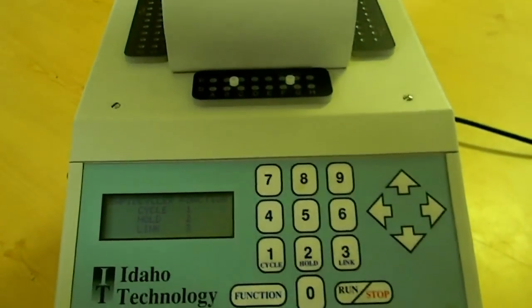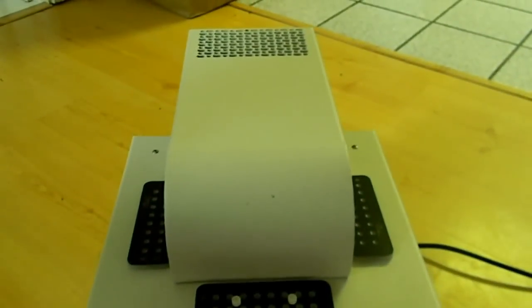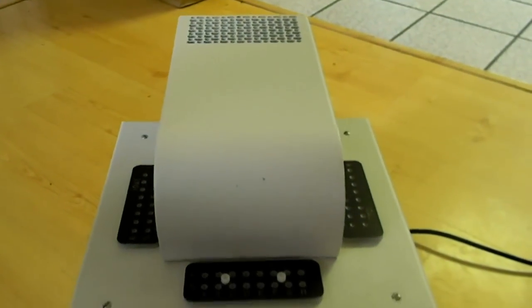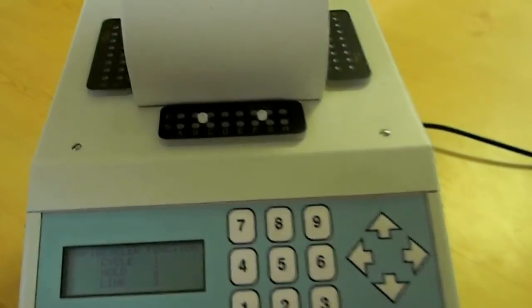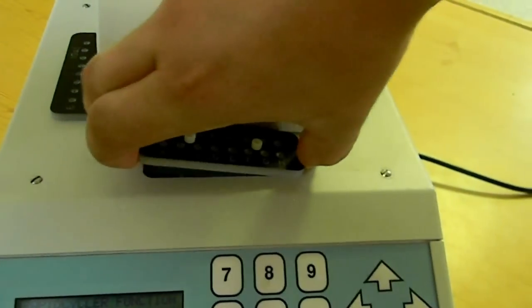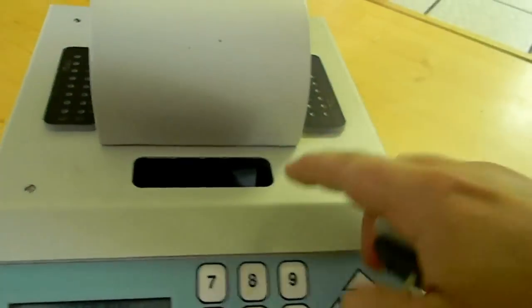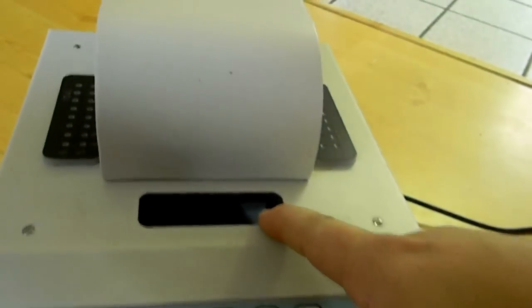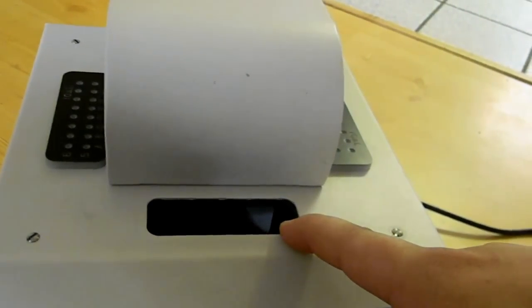Now this machine is a little different than conventional PCR machines because it doesn't use a Peltier element to heat and cool your samples. It uses a halogen lamp inside and then a fan to circulate hot and cold air. You can see that white rotor in there, that's one of the fan blades.